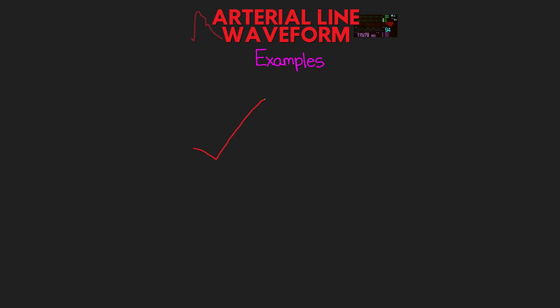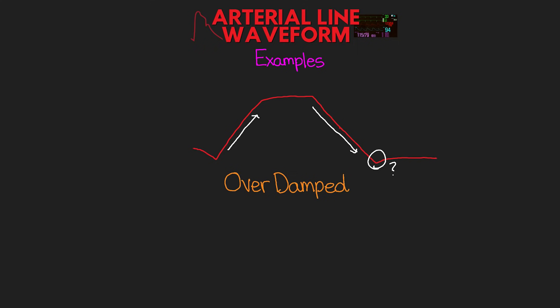One last example. Here again we do a square wave test — what would this be? Hopefully you saw that slower upstroke, a long exaggerated downstroke with no oscillation at the end. This would be an indication of overdamped. Knowing this, what would you expect to see for your patient's arterial blood pressure tracing? This should tell you that there is a loss of energy in the system. Therefore, you are going to see a flatter waveform, giving us a lower systolic and possibly a higher diastolic blood pressure.